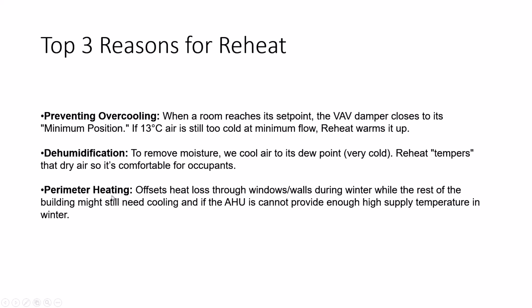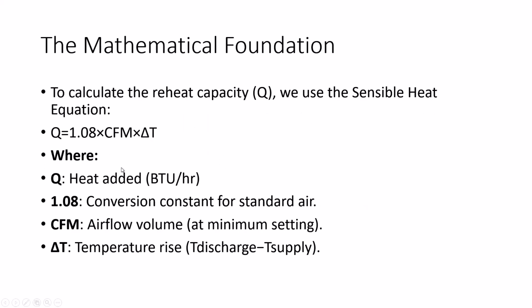For example, you have an AHU supplying cold air, and you need, say, 100 Fahrenheit air supplied to the room, but your AHU or RTU is not capable of doing this. So you need this reheat coil inside the VAV to warm it up to the temperature you require. So this is another reason. There are others also, but these are the main reasons.